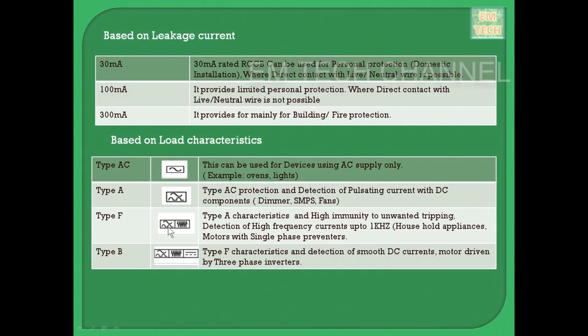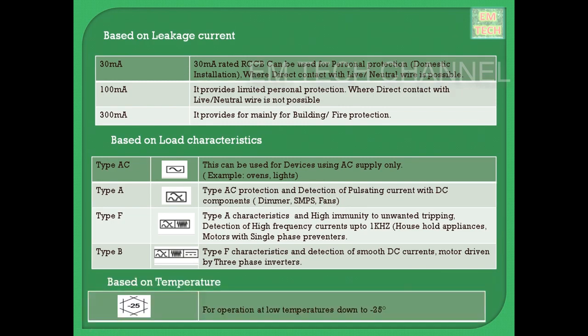Additionally providing type F RCCB functionality, it also detects smooth DC currents. The devices that use this type of RCCB are motors that are driven by three-phase inverters. You can see the symbol here. This is type AC, type A, type F, and this unique symbol for type B. And the final factor is selection based on the temperature. You can see here the symbol on the left shows the temperature at which the RCCB can operate. In this tabulation, it shows minus 25 degrees Celsius. Means it can be used for operation at low temperature down to minus 25 degrees Celsius.